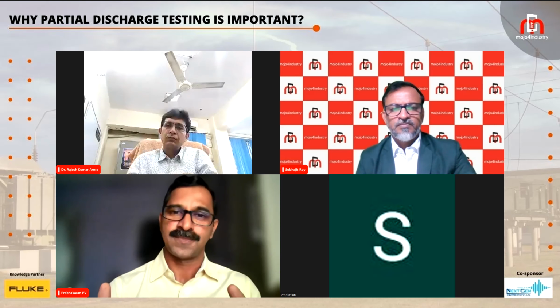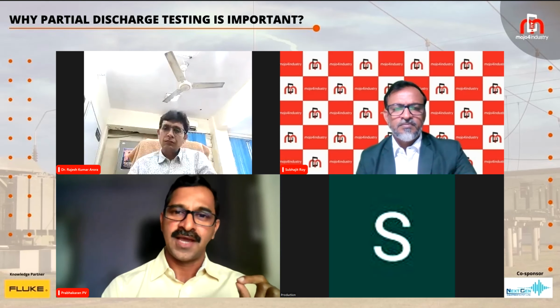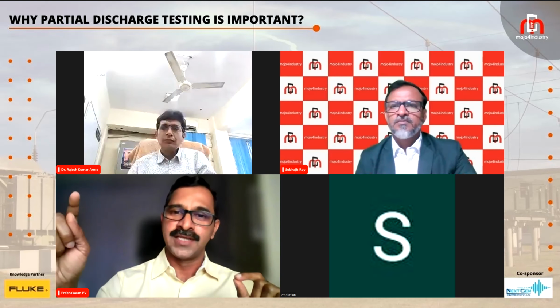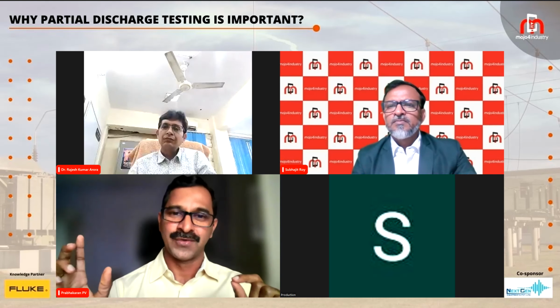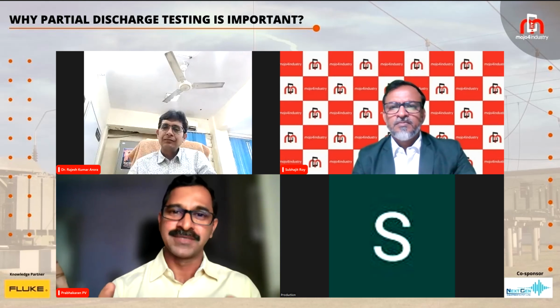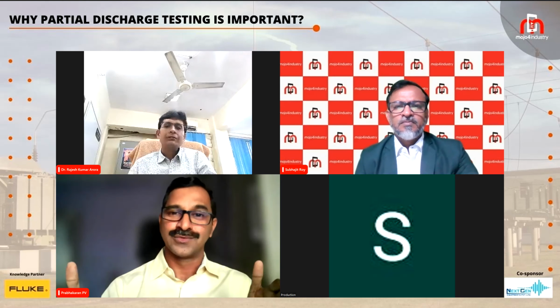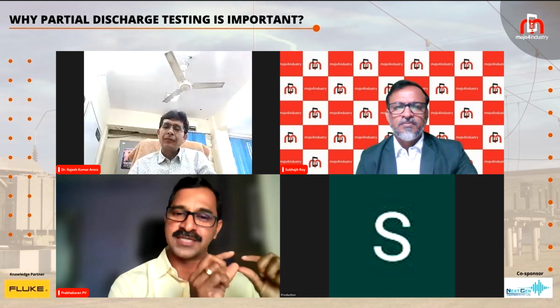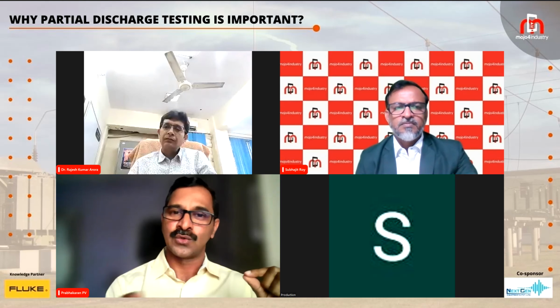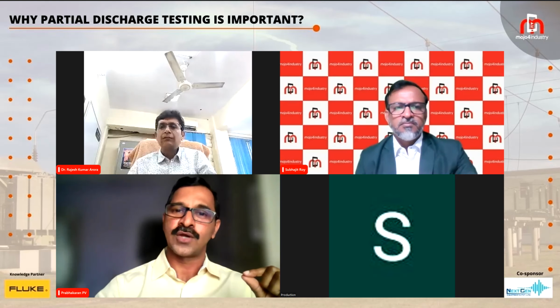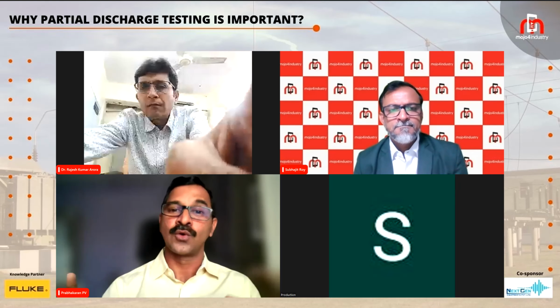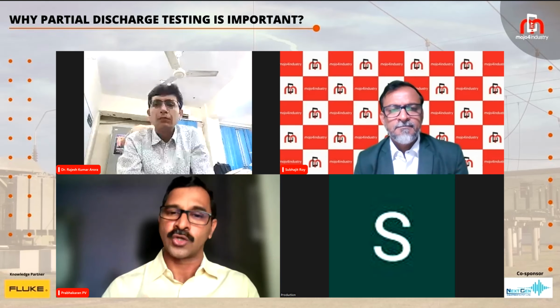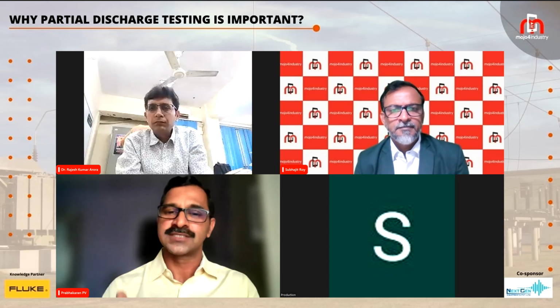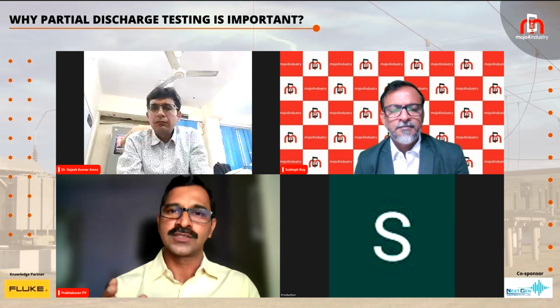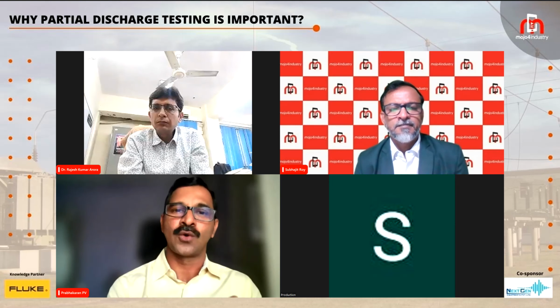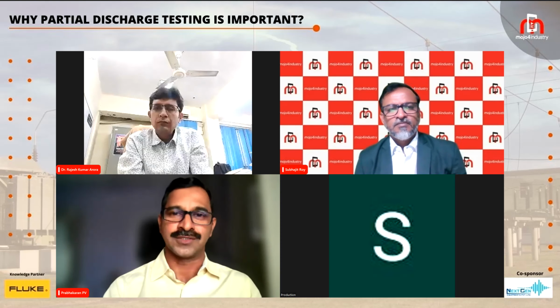Going back to why this needs to be detected - it's very important because partial discharge always starts small and grows, finally ending with a flashover or a catastrophic failure. That means during that time period you don't know whether the partial discharge detected today will fail or kill your equipment tomorrow, 6 months later, or a year later. You don't know. That's why you need to monitor it, document it, and have a precise mechanism to ensure that unwanted shutdown doesn't happen. That is what you have to ensure.